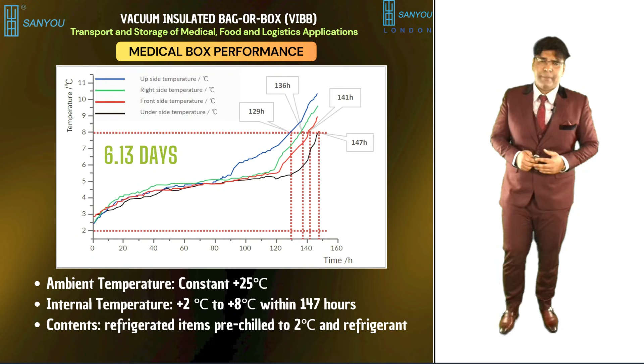The performance of the medical box is that at ambient temperatures of plus 25 degrees Celsius, the internal temperature was maintained between 2 and 8 degrees Celsius within 6.13 days, considering the contents which were pre-chilled to 2 degrees Celsius.